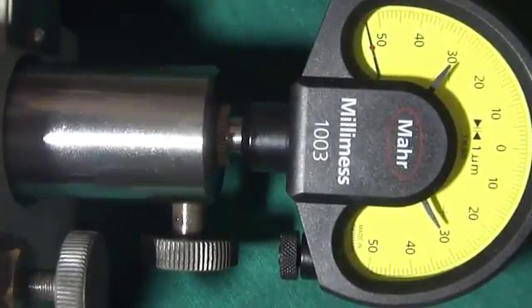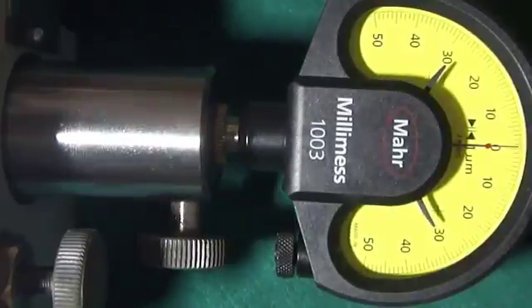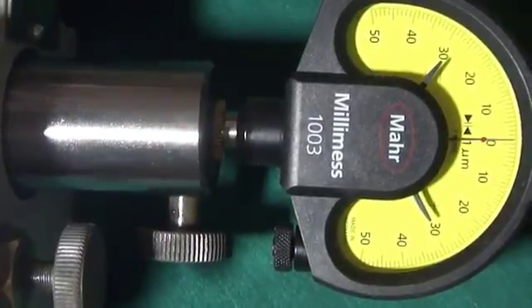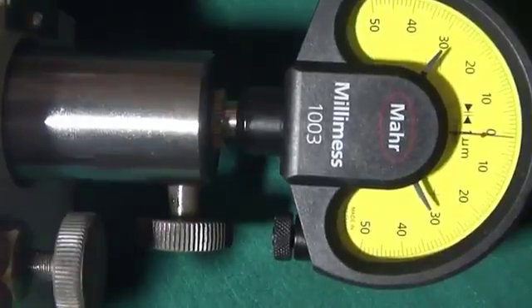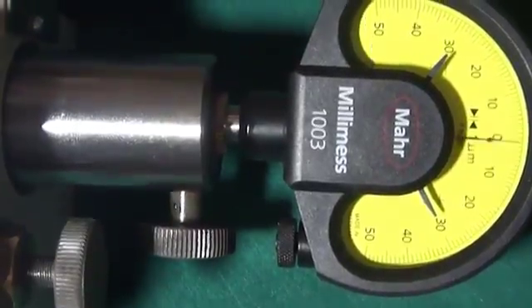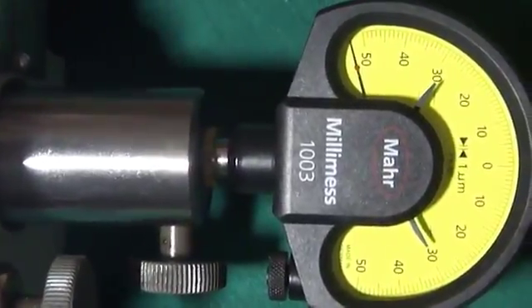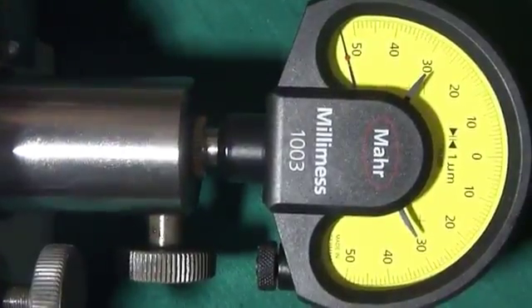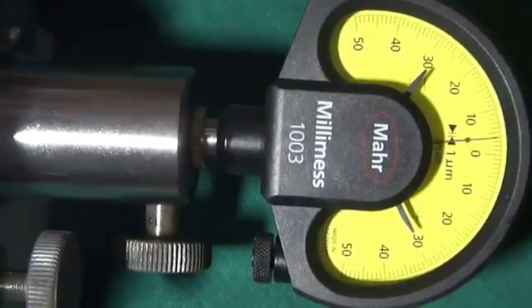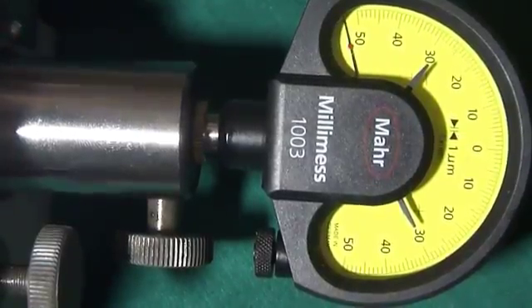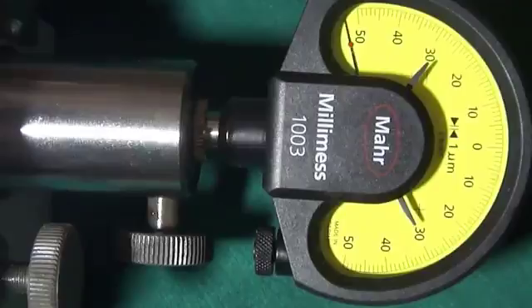We are taking readings now. We can see ovality of this bearing. We can show approximately 4 micron ovality is there in this ring.